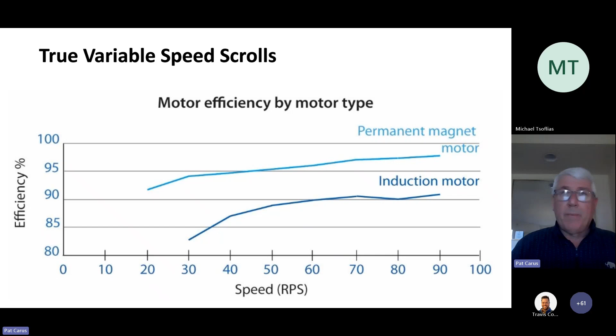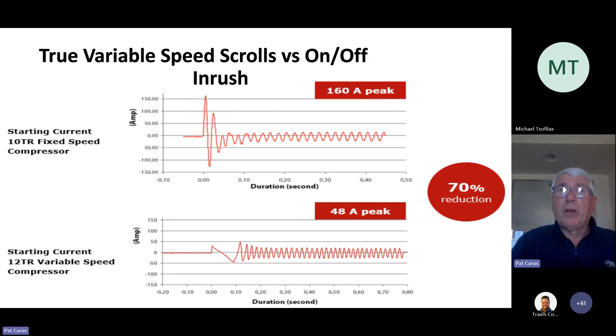The other nice part about a variable speed scroll is, as we do more electrification, the grid's capability to handle all of the things we're throwing at it is a bit of a problem. We're not well set for the grid to take all of this yet. But the nice part about variable speed and mag bearing is both have the ability to limit inrush, about the impact of a toaster, when you use a variable speed scroll or a mag bearing machine.